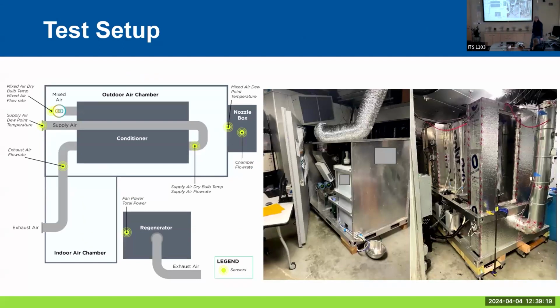Here's our little test setup that we did in our lab. We have an environmental chamber, two parts to it, an outdoor and an indoor air chamber. For this particular one, we didn't really use the indoor air chamber, and we put the unit inside the outdoor chamber, and we set the system to the mixed air conditions that we want. We brought in the mixed air through the system, and it produced the supply air where we measured the details of the flow and the air, and then we measured the exhaust air. We also had the regenerator and the control unit outside.